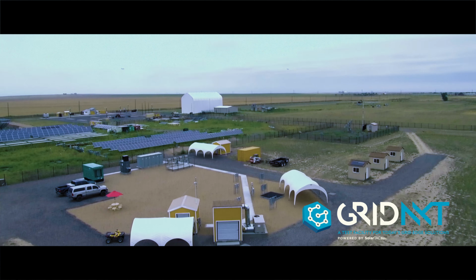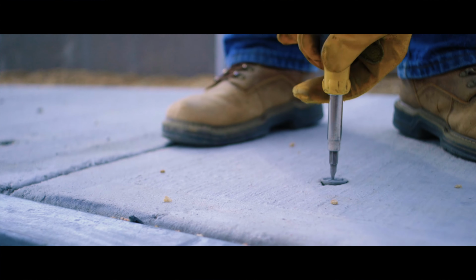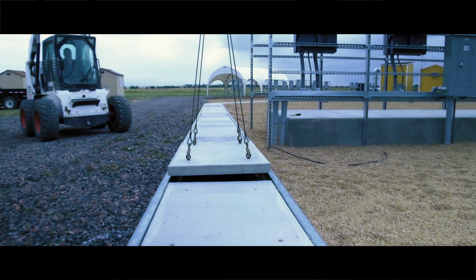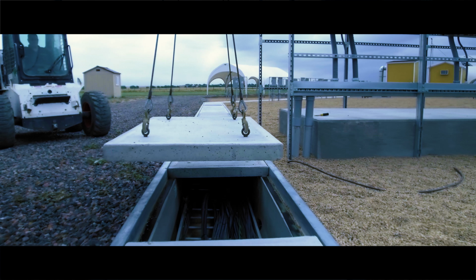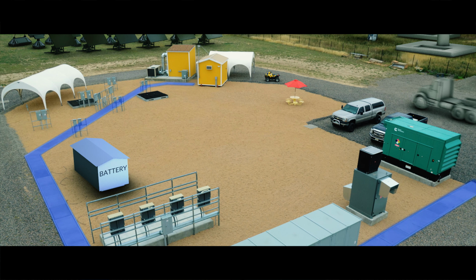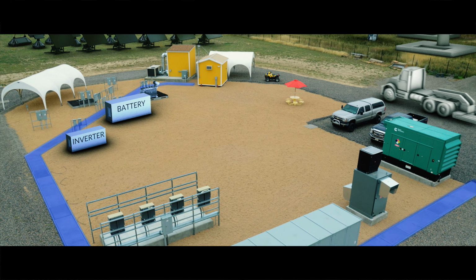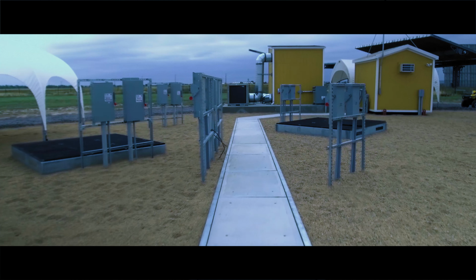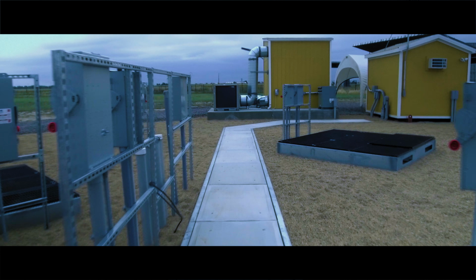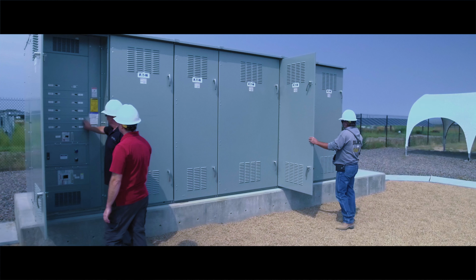It is a 1.5 megawatt plug-and-play, multi-user microgrid test facility. The center component is a tunnel system that allows us to reconfigure these assets that we have in virtually any way. And literally this is a $1.5 million infrastructure that we have built in sort of like a giant erector set. What this allows companies to do is to bring in generation technologies, hybrid systems, inverters, batteries, other balance of systems, other microgrid controllers, and really utilize our infrastructure for either very short-term or very long-term testing.